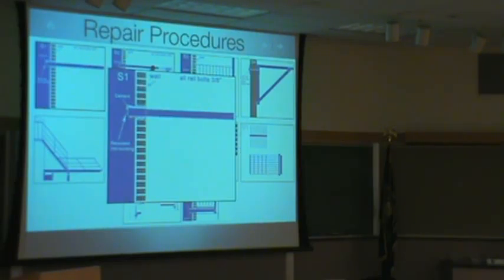Right here — egress balconies, fire escapes, egress balconies shall be examined and/or tested. What does that mean — examined and/or tested? Who has that choice — the structural engineer or you? You do. It'll be examined and/or tested for structural adequacy and safety every five years by a Massachusetts registered professional engineer, or others qualified and acceptable to the building official — meaning, can we send you credentials for our fire escape engineer or inspector? And said engineer shall submit an affidavit to the building official. That's a building code from your sister city — you may want to copy it.